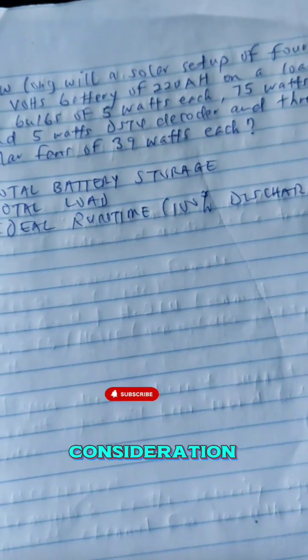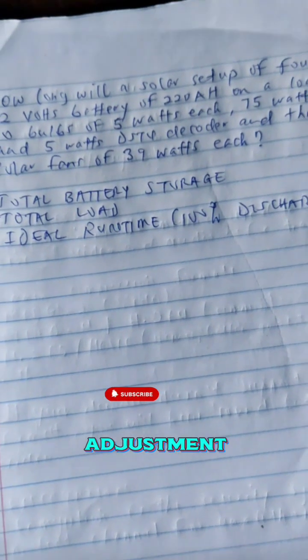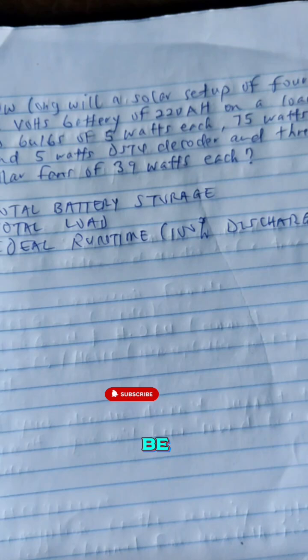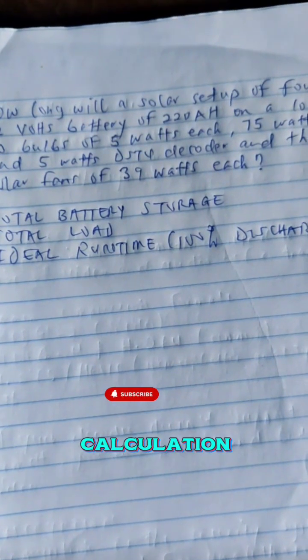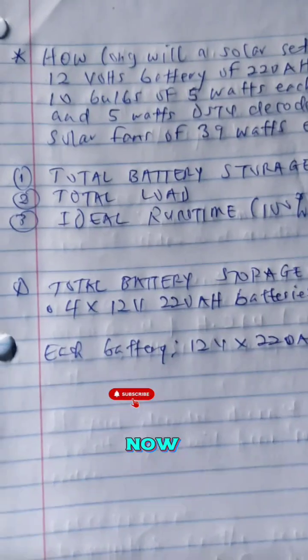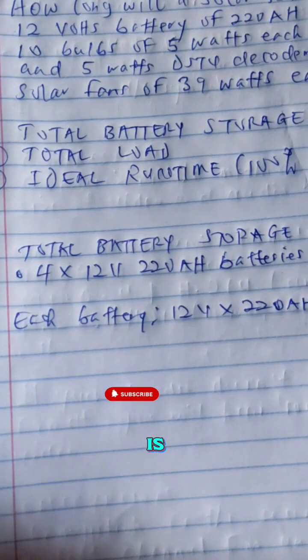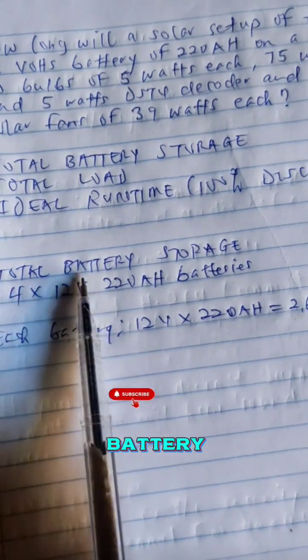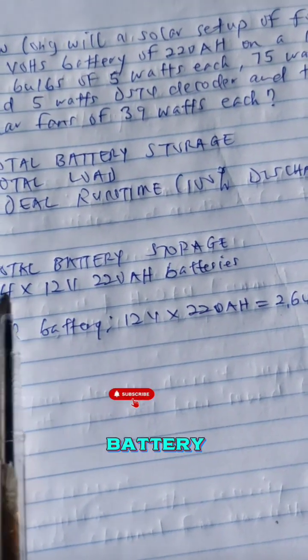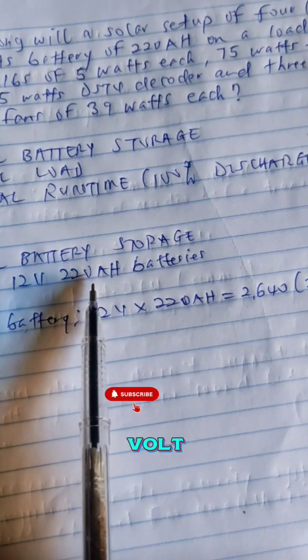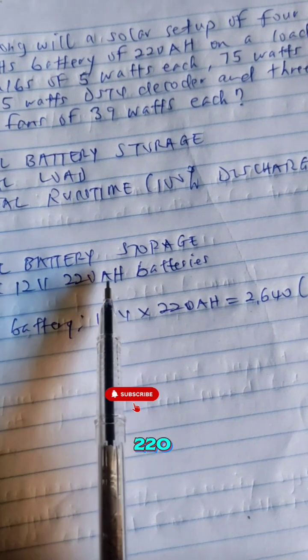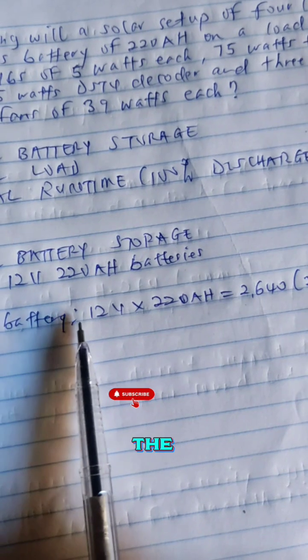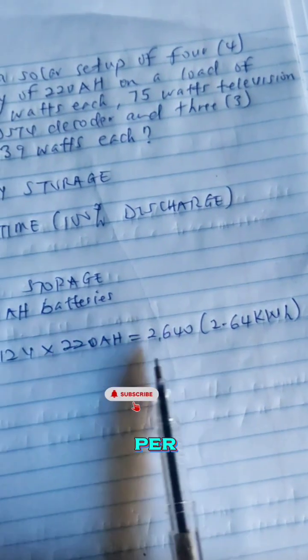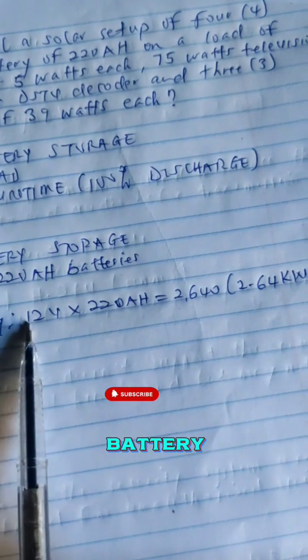First and foremost, let's calculate for the battery. You can see here is total battery. We have 4 batteries of 12 volts, 220 ampere hour. So for each of the batteries, the watt hour is going to be 12 volts times 220 ampere hour, which gives us 2,640 watt hour. This is for each of the batteries.